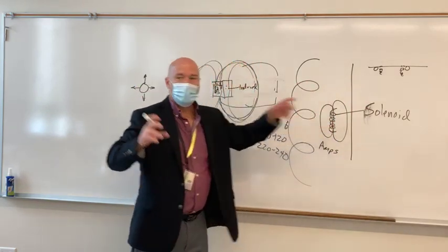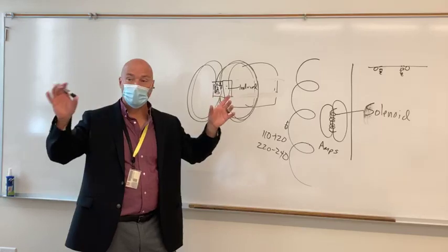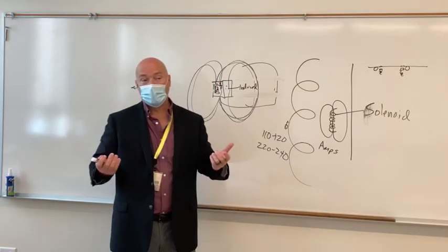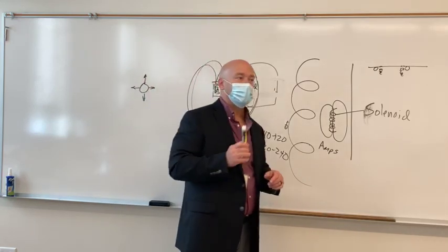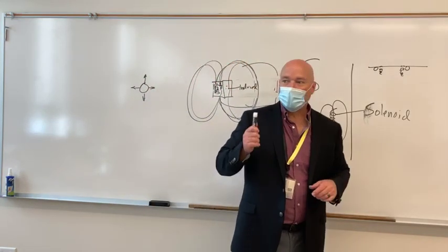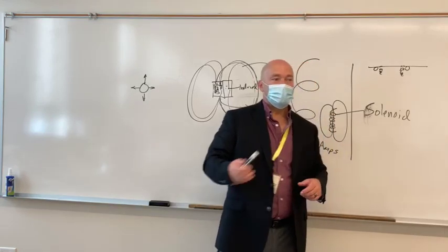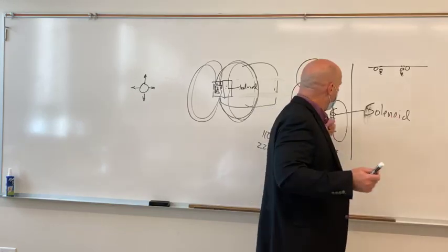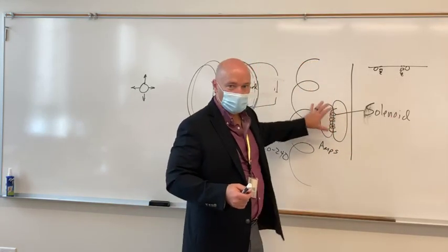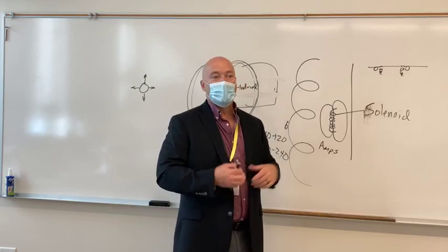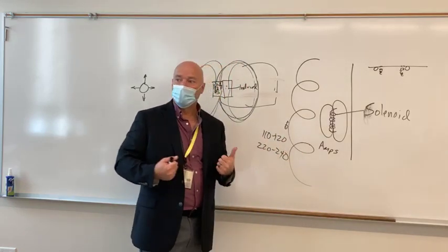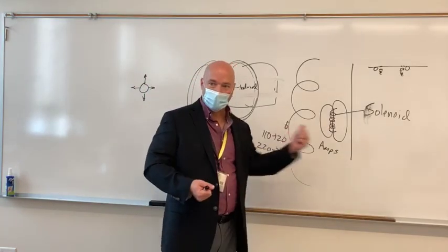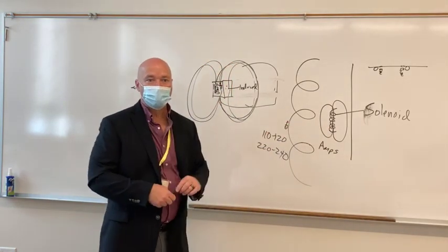It's a solenoid. And it's a very strong magnetic field, so that if you just walk up to the door and try to shut it by hand, sometimes it won't shut, because some of the doors in the hospital, by regulation, need to stay open unless there's a fire. And once the fire alarms go off, they turn off the electricity to those solenoids and then the doors close all by themselves. So some of those things, you can't make them close. You can pull on them all day long, and the magnetic field is so strong that you can't pull the doors away from the solenoid.